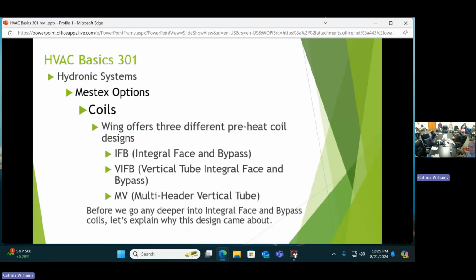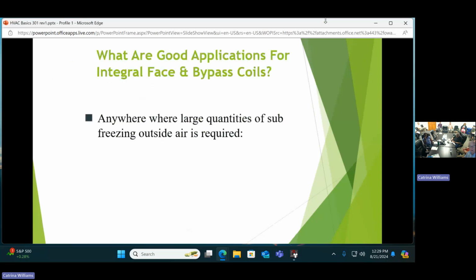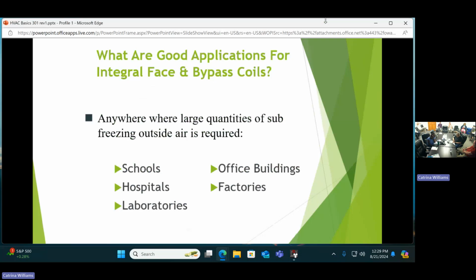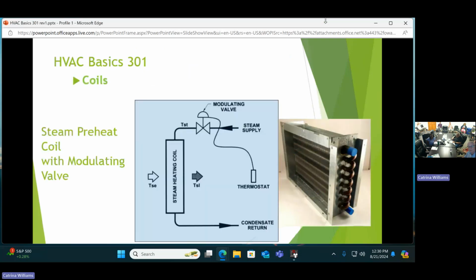Okay. And so we're going to go deeper into the IFB coils themselves. We're going to give you a little bit of an idea of where they might be used and why. Basically, whenever you're bringing in large quantities of sub-freezing outside air, you want to preheat it so you're not putting cold air directly into the space or components that might be damaged by that. Some of the applications are schools, universities. Doug can probably mention at least a dozen big campus universities where our coils are all over the facility. Hospitals, surgery centers you've mentioned, just general rooms in general, laboratories, office buildings and factories all bring in large amounts of outside air for various reasons. And whenever you bring that outside air in, you want to preheat it the best you can. But you don't want to bring in a bunch of air at -20 if you're up in Minneapolis.